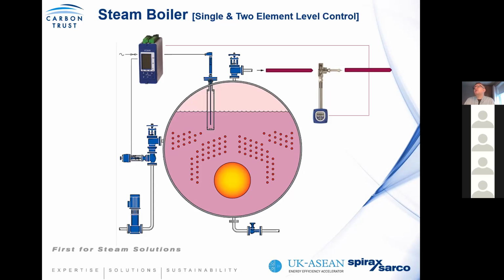And what it does is that if there is a high steam demand and there is a potential for swell, the two element control would have different stages in working level, in other words, to allow you to maintain a continuous flow of water into the system. So where your process is batch orientated, or you find your steam demand is very much on off, as a minimum, you need 2-element control. And again, where it's employed, we have achieved anywhere from a 3 to 5% boiler efficiency gain. Because where it's not employed, we have also found that where you get a reduction in pressure, the second boiler has to fire to maintain the steam demand. So you could find that putting in 3-element control means that you can operate with a single boiler.